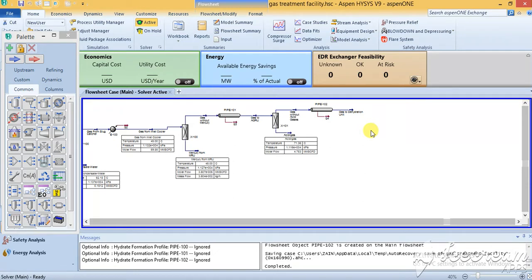Otherwise the pressure at the downstream, where we are getting the FCV or at the tie-in point, will have huge pressure differences because of these 10-20 kPa losses, and we will not be able to make the exact assumption that this much pressure will be at the bottom of the FCV or downstream of the FCV. So basically I've already considered the pressure drops across the piping section. So the gas to the dehydration unit has already been taken.